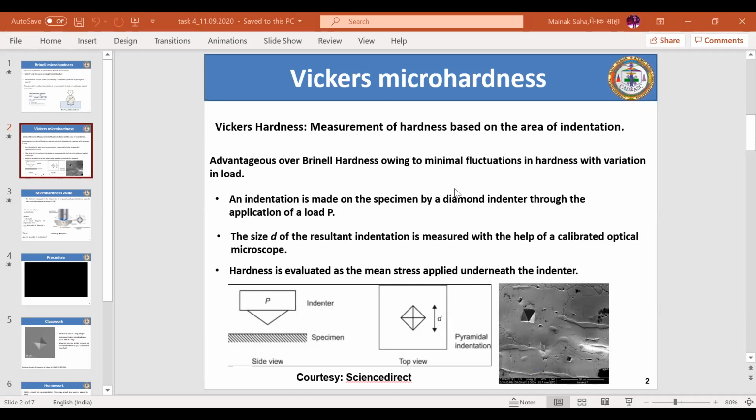What you essentially have to do is, when you increase the load, you should first ensure that your hardness value does not change. For example, if you are doing the testing at 1 kg of load, if I am showing you this, this is the indenter. And this is not the indenter, this is the surface, rather the support of the indenter, not the surface also.